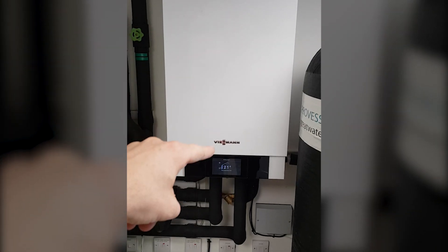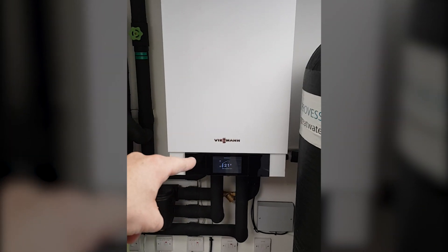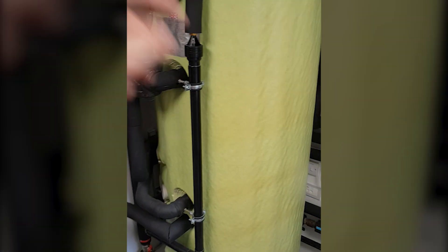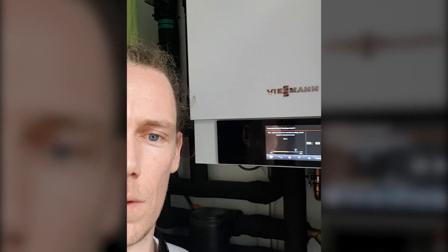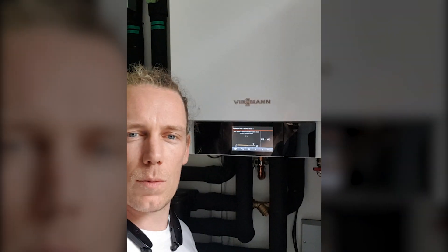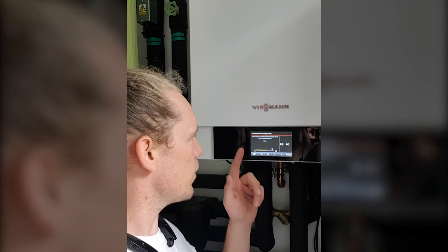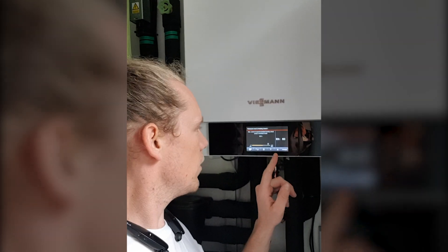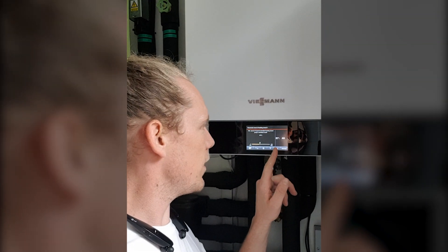This boiler here supplies all the radiators in the house, warm air unit, and this cylinder here — all without hydraulic separation. And that's with a max pump speed of 60%, minimum pump speed 40%.